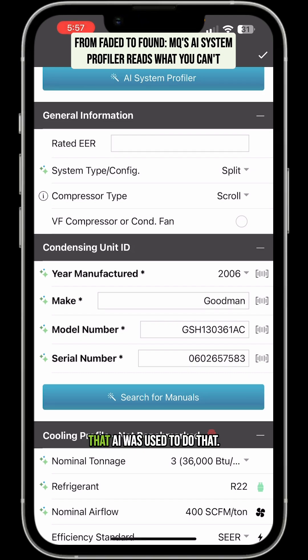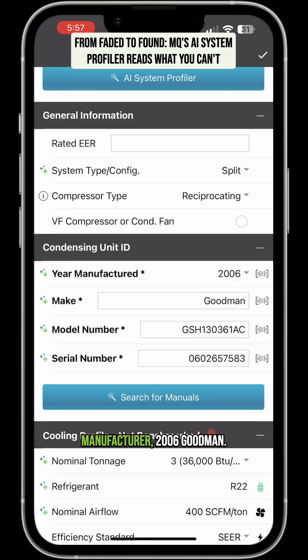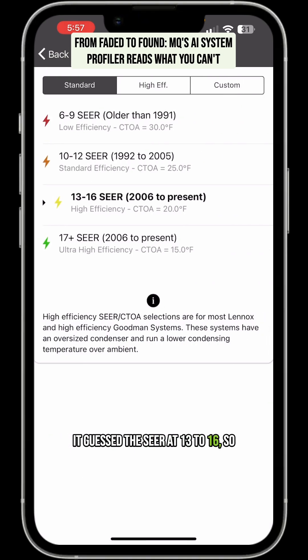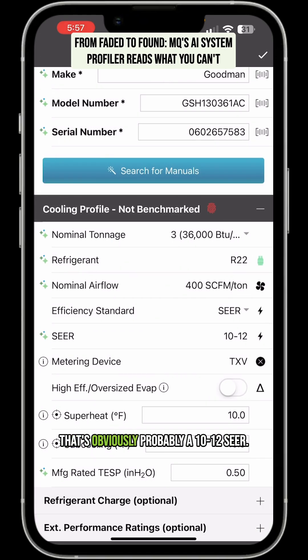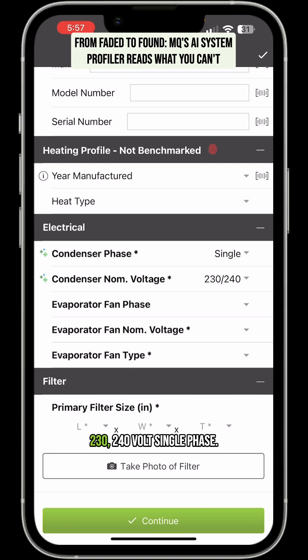Those green-blue symbols are showing that AI was used to do that. So we would just select it — it's got a reciprocating compressor. Year manufactured: 2006, Goodman. It got the model number nailed at GSH130361AC, got the serial number off there, set it up for three ton R22 at 400 CFM per ton. It guessed the SEER at 13 to 16, so we would go ahead and change that — it's obviously probably a 10 to 12 SEER. And it got the condenser at 230/240 volts single phase.